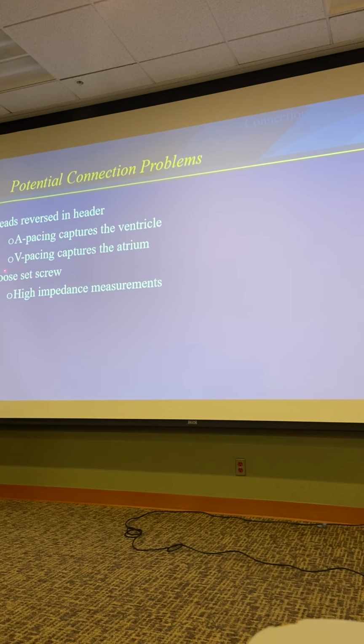If the set screw is not screwed down tightly, you get very high impedance. That's the easiest kind of high impedance problem to fix, and that would be noticeable while the patient is still on the floor, before they go home. All of these folks get checked the next day, and if the next day check shows a high impedance, then that's a set screw problem. If it's not there then, it's not going to be a problem later on. That requires a trip back to the operating room, tighten it down, and you're good to go.